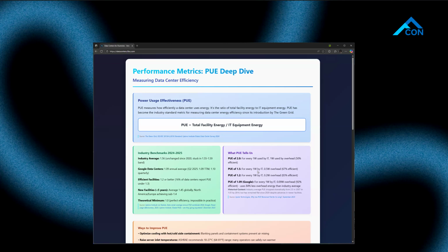There's some efficiency metrics that data centers do look at. You have the power usage effectiveness, which measures the ratio of how much power the data center consumes to how much the IT equipment is consuming. You have all of the auxiliary systems of the data center that also have to be powered, like generally the AC systems, the lights, all of that equipment. But the main focus of the data center is your IT equipment, because ideally you want that ratio to be as close to one as possible, because everything that's not the servers and network equipment is the overhead. So generally you want to try to reduce the overhead as much as possible.